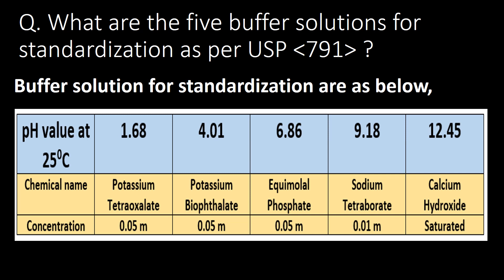What are the five buffer solutions for standardization? As per USP chapter 791, you can refer to the table below for buffer solutions used for standardization. The table provides pH values at 25 degrees Celsius, chemical names, and concentrations. The five buffer solution pH values at 25 degrees Celsius are: 1.68, 4.01, 6.86, 9.18, and 12.45.